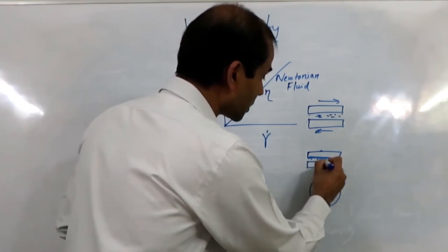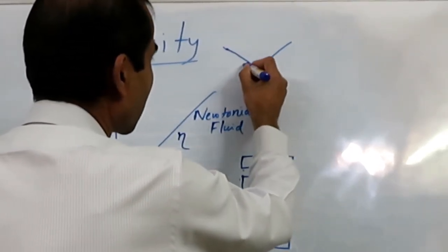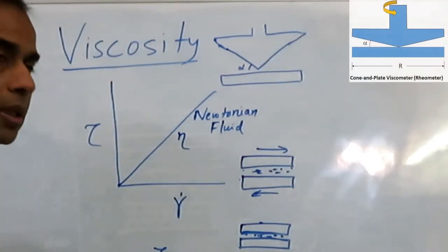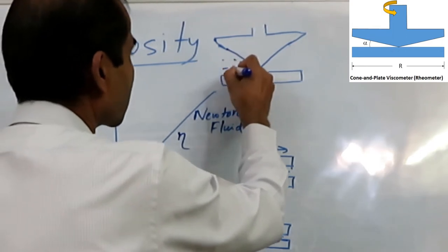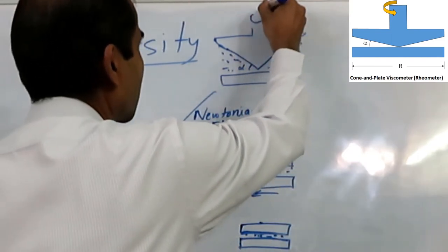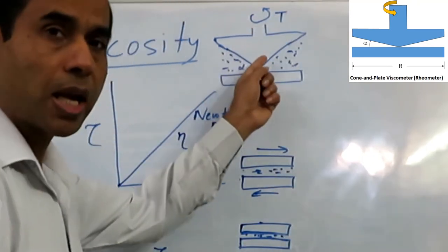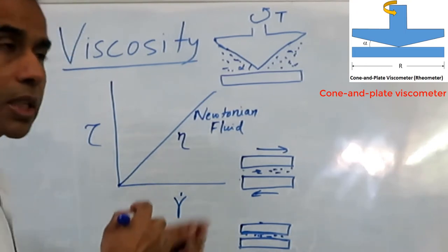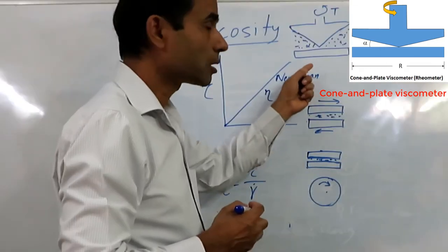One problem with the parallel plate method is that getting two perfectly parallel plates is quite difficult. To solve this, the top plate is made in the form of a cone with a very small inclination angle, and the bottom plate is a circular disc. This is called the cone and plate geometry. We fill this geometry with the liquid, and we can measure the shear stress by measuring the torque applied. There is an equation to find the viscosity in this geometry, and this is what we do in the rheometer.